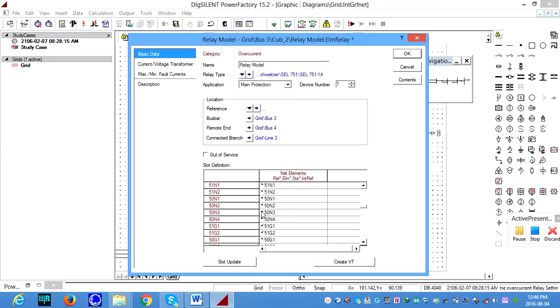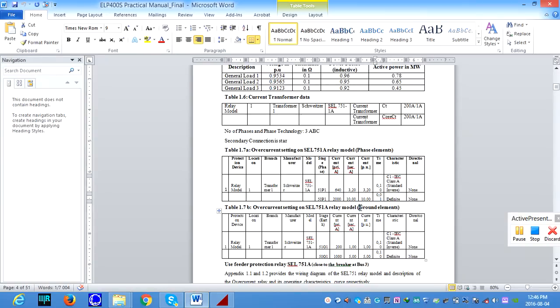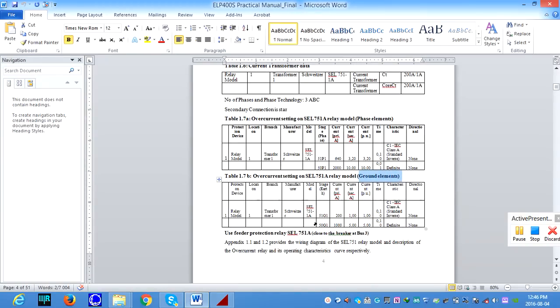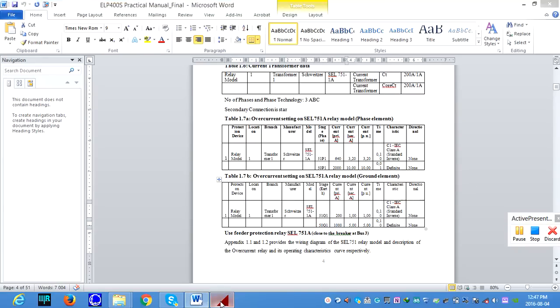Okay, so if you see here, the tick means it is in service. This something like a dash means those elements are not in service. Okay, then we're coming to 51G1, that is a ground element setting. Refer back to the manual, it's the ground element settings. So if you look here, your 51G1 is giving 1 ampere secondary, okay, and 0.10, and the current for the 50G is 5 amperes and 0.10. So we make sure of the 51G1 and 50G1 elements, but first we are focusing on 51G1, 1 ampere and 0.10 seconds.